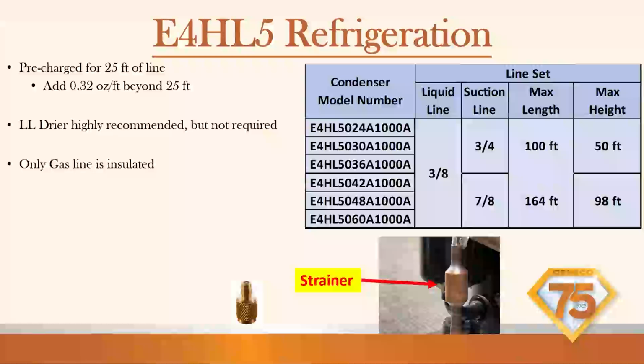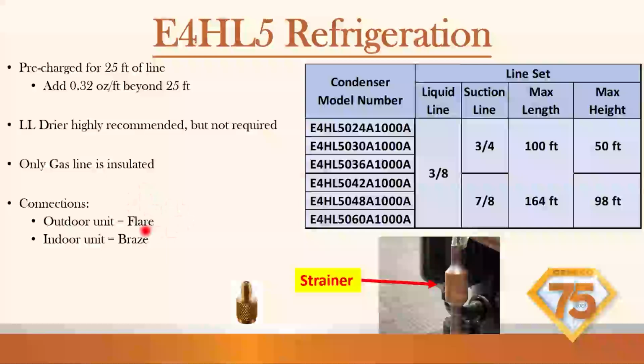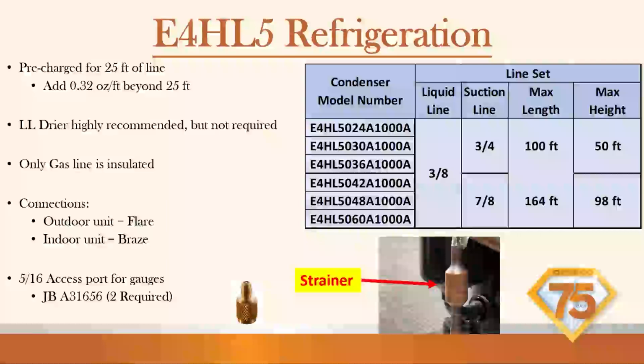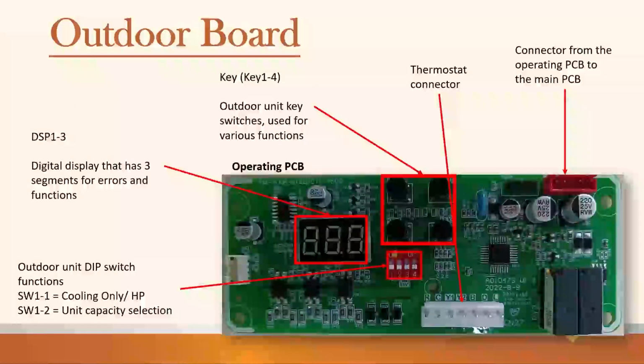Only the gas line is insulated, so the 3/8 liquid line does not need to be insulated. Outdoor unit has a flare connection; indoor unit is brazing. There's a 5/16 access port, so you will need the 5/16 adapter. There is no true suction line on this, guys. Sorry. So you will not be able to pull a true suction pressure in heating mode. Best way to do it is the pre-charge for 25 foot if you're in heating season, and then come back and refer to the data plate for what subcooling it is in air conditioning mode. Most likely 10 degrees subcool, but always refer to the data plate because it's possible it changed.